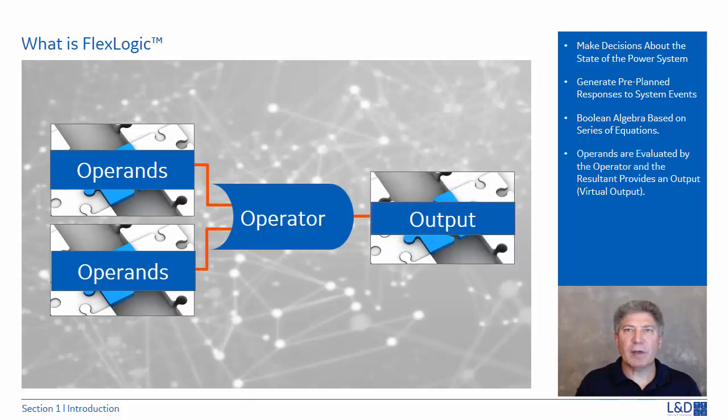The operands are evaluated by the operators and the resultant provides an output. The equations are based on reverse Polish notation, which means it begins with entering operands or some type of input. It becomes evaluated and the resultant is stored in an output. These equations are evaluated every two milliseconds.